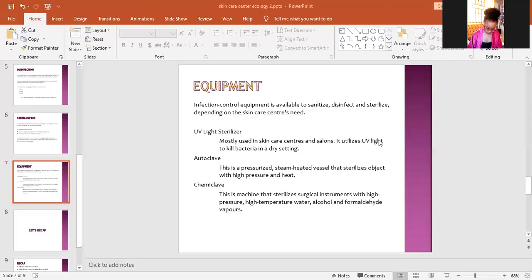So in a nutshell, they mean that you should consistently check if your autoclave is functional, if the amount of heat that is meant to come out is still being generated, and if it's still able to kill spore bacteria. Don't just leave it and say, okay, it works today. Because how will you know if there's no spore bacteria on that equipment? You need to test it, and that's where your test strip comes in. So use your test strip and follow the manufacturer's instructions to test if it's still able to kill spore bacteria.